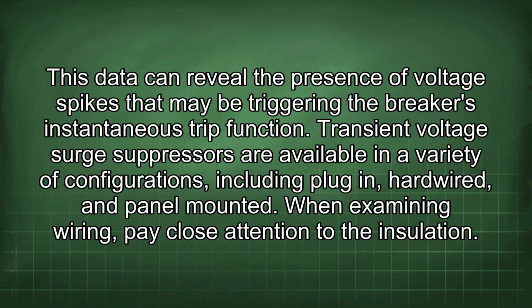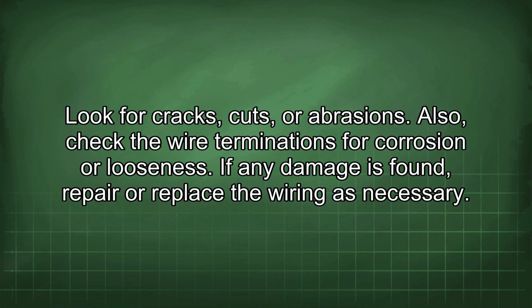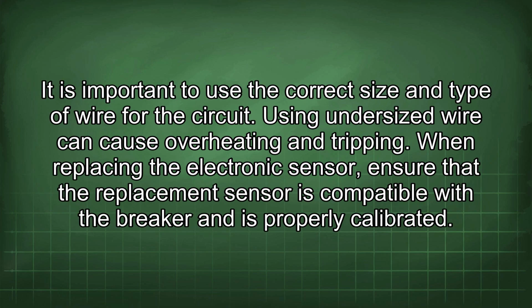When examining wiring, pay close attention to the insulation. Look for cracks, cuts, or abrasions. Also, check the wire terminations for corrosion or looseness. If any damage is found, repair or replace the wiring as necessary. It is important to use the correct size and type of wire for the circuit. Using undersized wire can cause overheating and tripping.